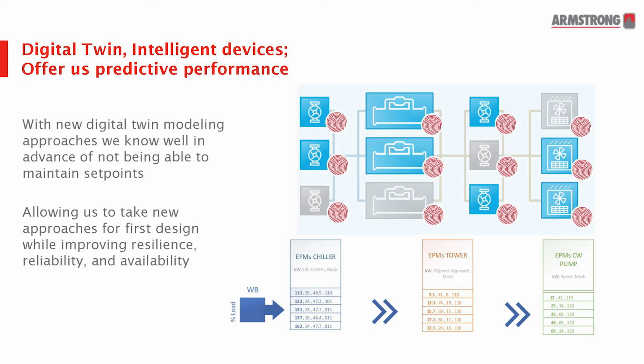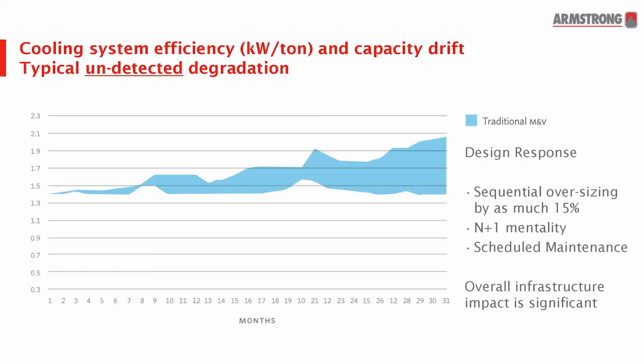When we started down this path approximately 6 years ago to do a purely digital machine learning environment without any equations, it was going to take the fastest commercially available computer 99 years to calculate the best combination for a 26-dimension chiller plant - that would be a 5-chiller plant. With the advancements of some mathematical geniuses we employed, and also the advancement of processor speeds and the availability of cloud learning - incorporating historical sites and the learnings we have on them - we're able to get that learning cycle down on a local processor to less than 2 minutes.